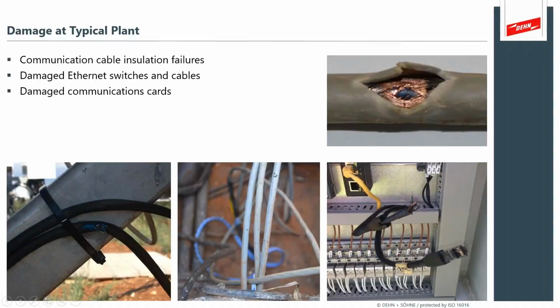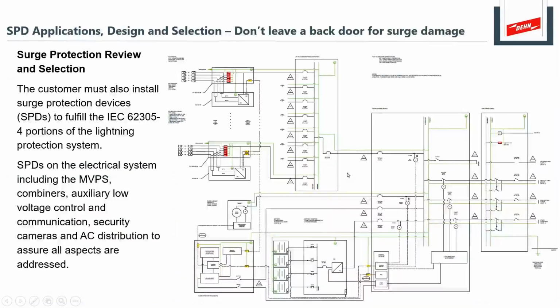So there's a lot of damage that can be incurred that you don't even see, because it's buried within the rest of the system, and it's not brand new anymore. This is almost like lightning fatigue in an electrical system. You can see the results with jacks being blown apart, but you don't necessarily see it in all those hidden cables. So when we have an opportunity to examine it top down, what does your one-line diagram look like?